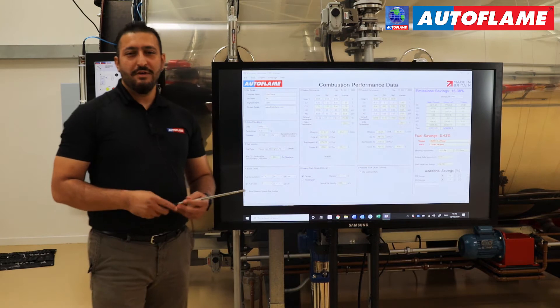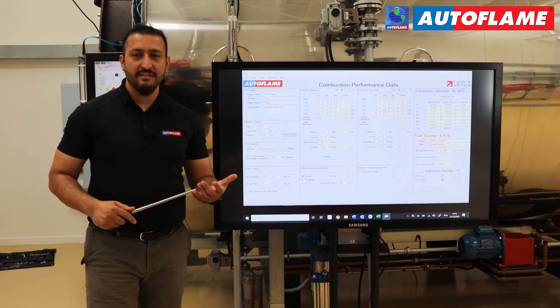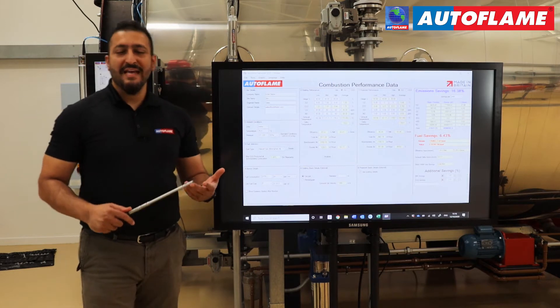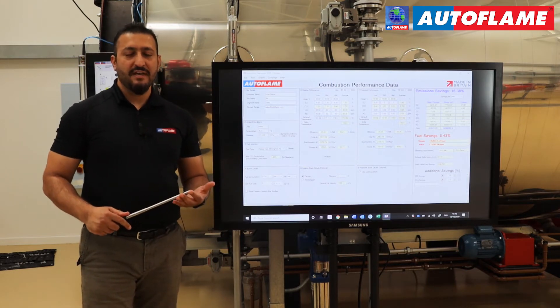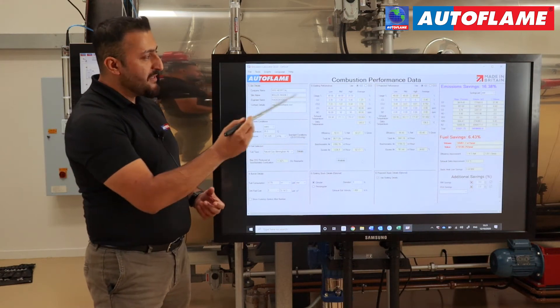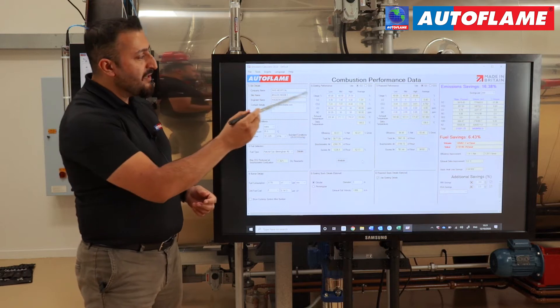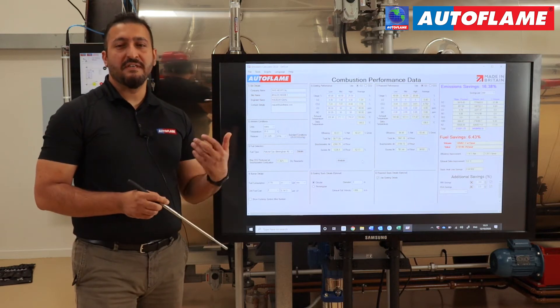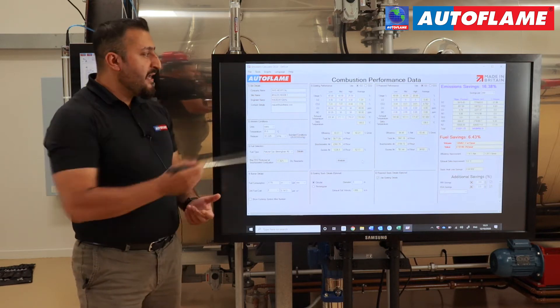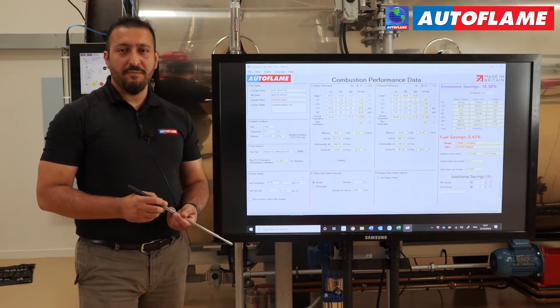In order to use this software, the typical data we need is the O2 readings, CO readings, your stack temperatures, your fuel usage, and the fuel cost. The new emissions calculator has been divided into eight different sections. Anything which is yellowed out is information which it automatically calculates. Anywhere with white boxes, that's where we need to put the information in.